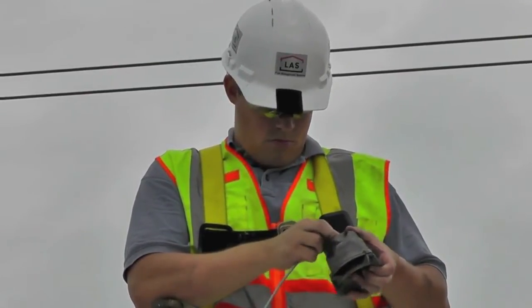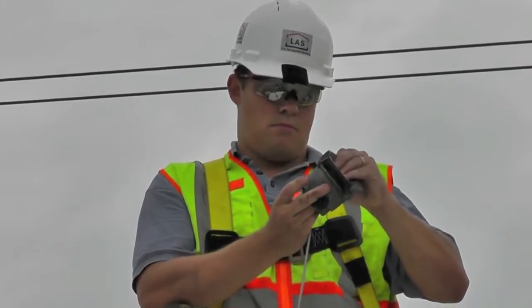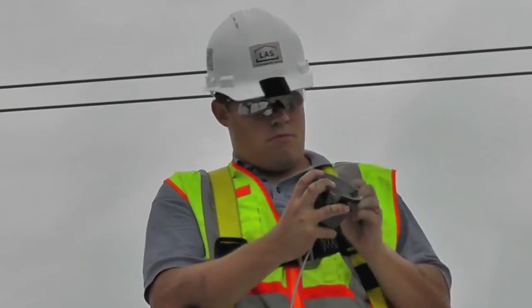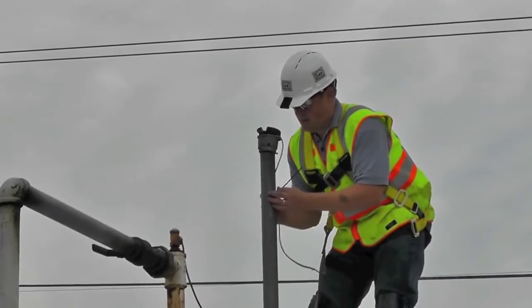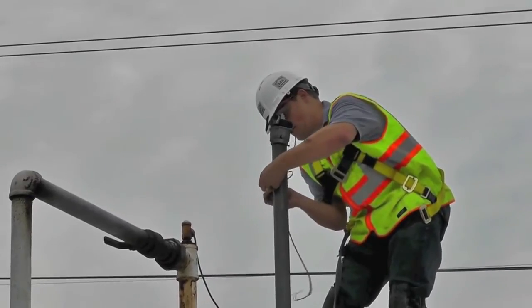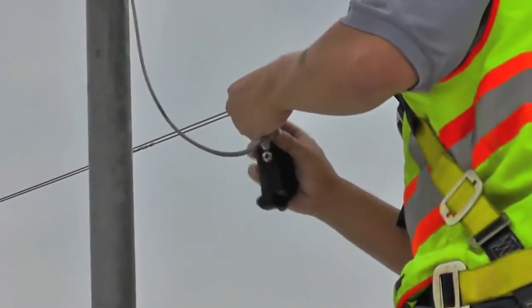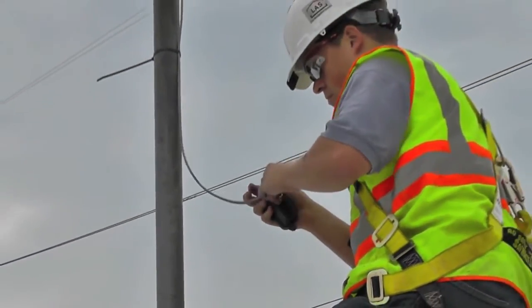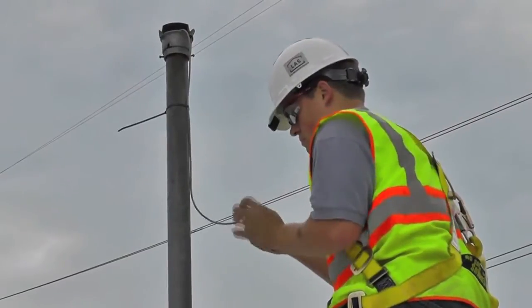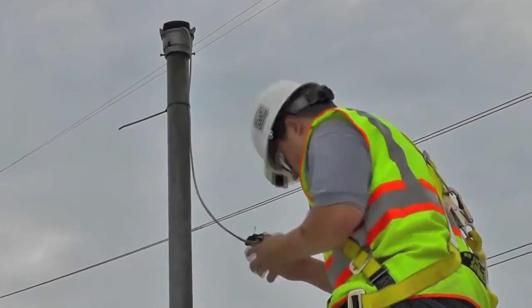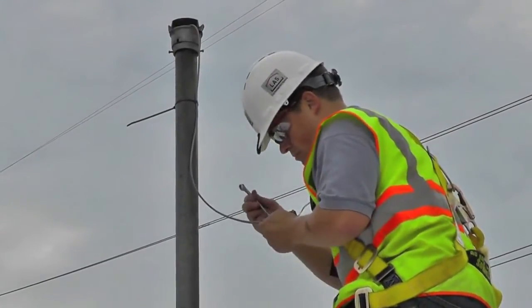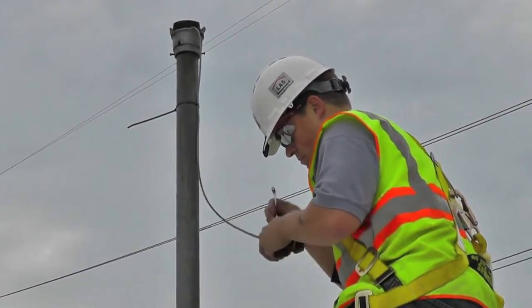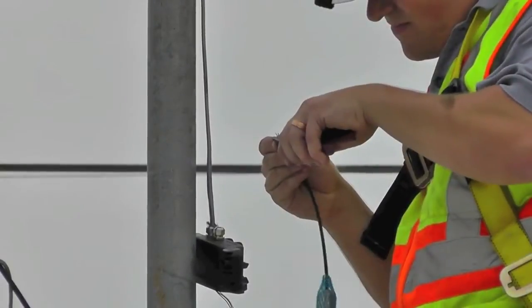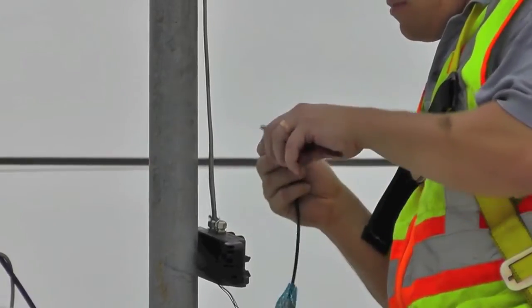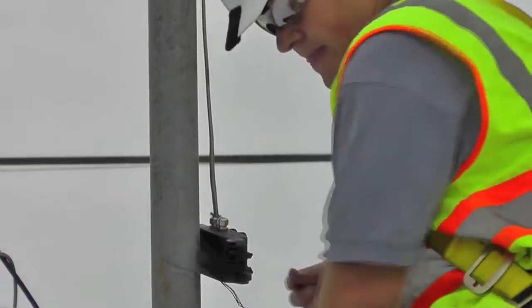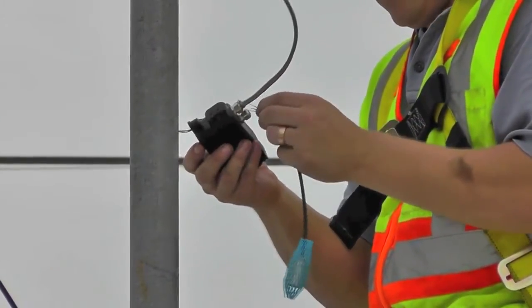The pressure sensor is then run through the bottom of the monitor housing and secured. We now install a second sensor inside of the monitor housing. The sensor is used to measure the atmospheric pressure. The basic principle behind this measurement technique is called differential pressure measurement. The pressure sensor inside of the tank measures the pressure of the fluid, which increases and decreases depending on the volume. The monitor is designed to detect the difference between the fluid pressure and atmospheric pressure. Once the tank has been calibrated, volume and height can be calculated using dimensions and specific gravity of the fluid.